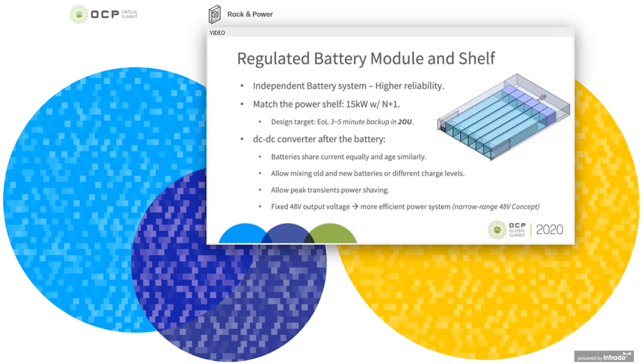Thank you. Hey, this is Hamid back. Another important piece of this project is a battery backup system. We are planning to design an independent battery system to have higher reliability. Basically, the battery system doesn't rely on the power shelf to operate; it runs completely independently. In terms of power, the battery shelf will match the power shelf with 15 kilowatt output power with N+1 redundancy. We are targeting the design of a 3 to 5 minute end-of-life backup time in a 2 OU shelf.